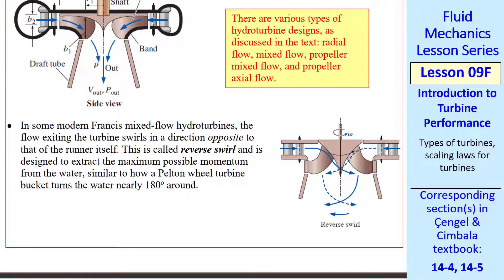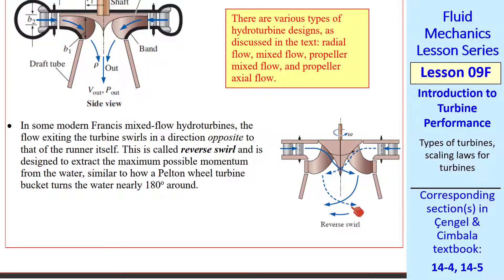In some modern Francis mixed flow hydroturbines, the flow actually exits with swirl opposite to the direction of the turbine itself. Why would they do that? It's similar to the Pelton wheel, where we try to turn the water 180 degrees — we can extract more momentum from the water by having some reverse swirl.